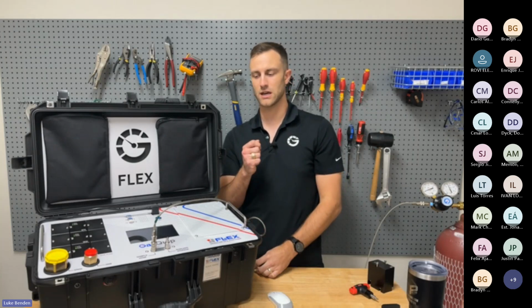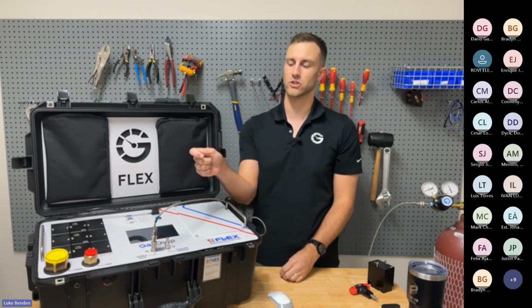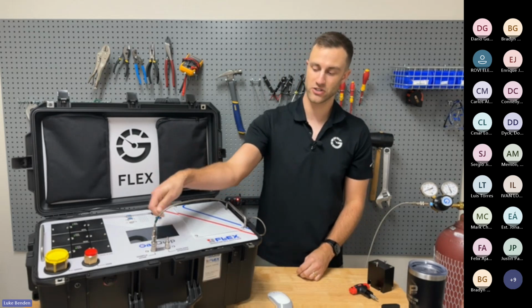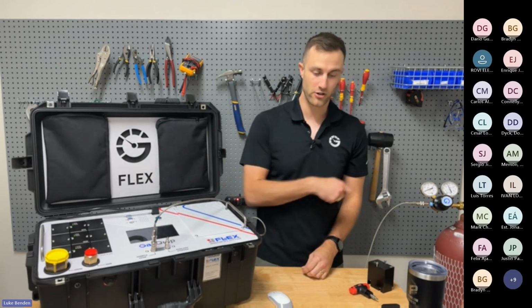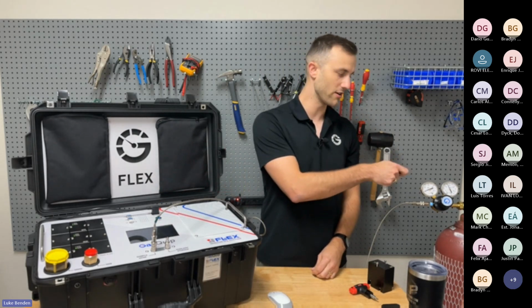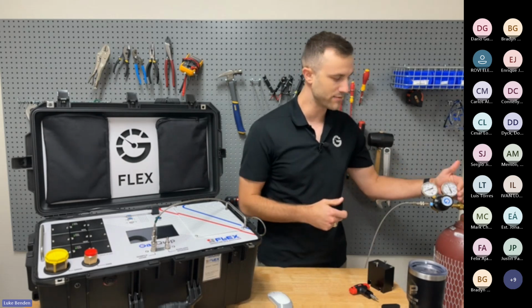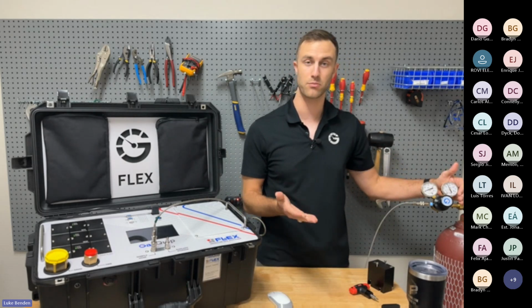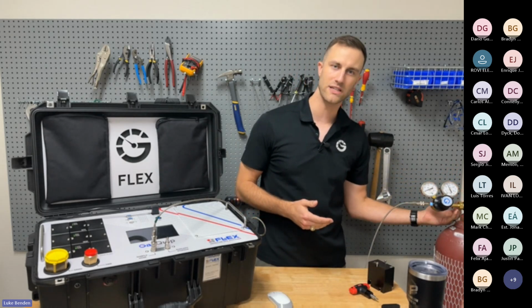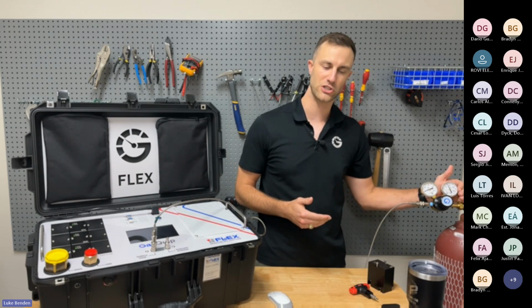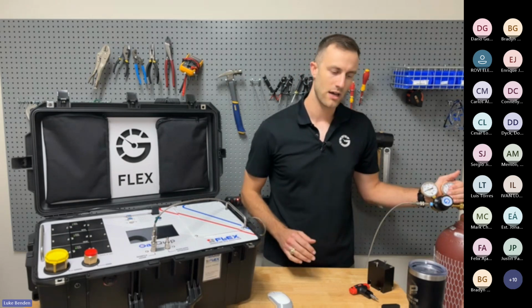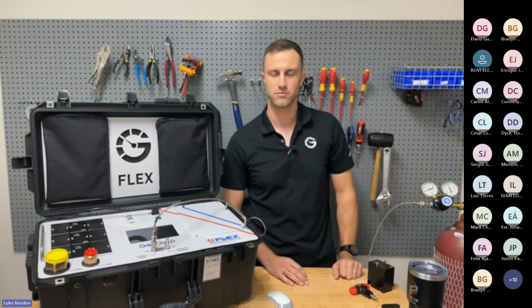You can also take an SF6 leak detector, check your hose, check your connections on the front of your analyzer, and check your connection on your cylinder to make sure you're not leaking anywhere. Sometimes the CGA connection can get messed up and have a leak coming in from the cylinder connection if you're testing a bottle of gas. Those are just some general places to start before you start ripping the analyzer apart.